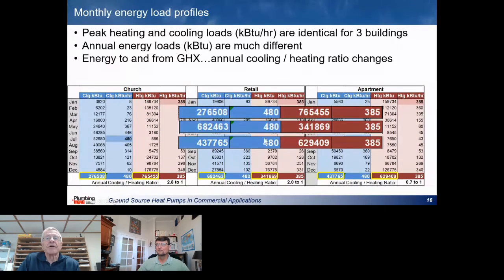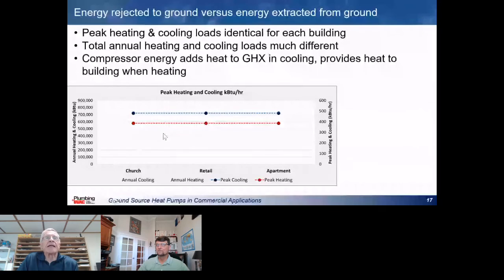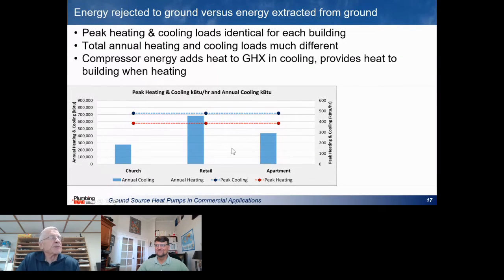So if we look at this, 480,000 BTUs, 385, they're identical. This one's much bigger in the amount of heat that we're extracting from the dirt than how much heat we're dumping back into it. This one is exactly the opposite. This one's somewhere in between. So what that means is that if you're looking at the peak loads and designing your system based on that, and I'm saying designing in quotation marks, it doesn't really reflect how much energy you're dumping into the ground or pulling from it. This is how much heat you're dumping into the ground from the church, the retail store, and the apartment. This is how much heat you're extracting. And that difference is pretty significant.